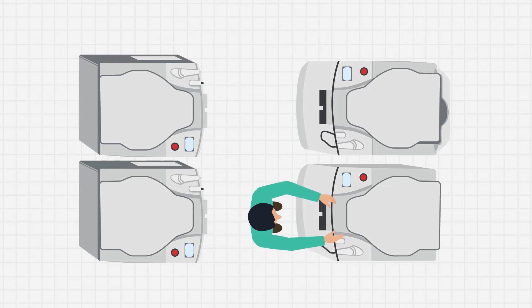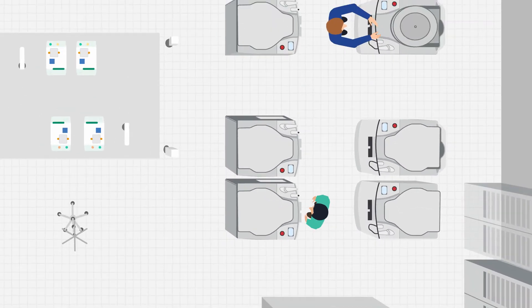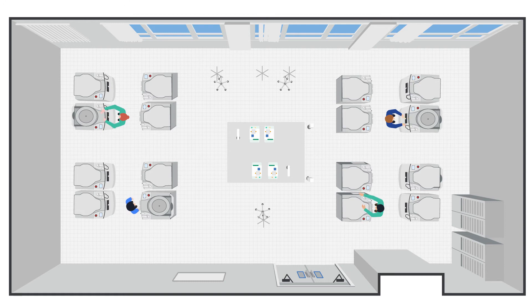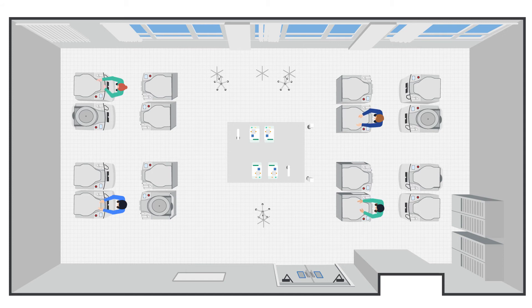It also requires only one operator to complete processing whole blood on four devices. The pod system allows the operator to easily handle the loading, unloading, filtration, and addition of solution to the blood bags, even in a small space.